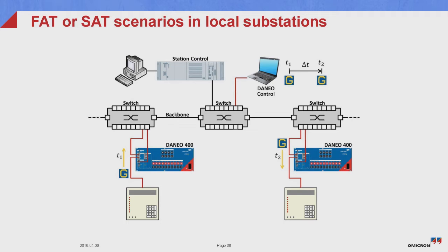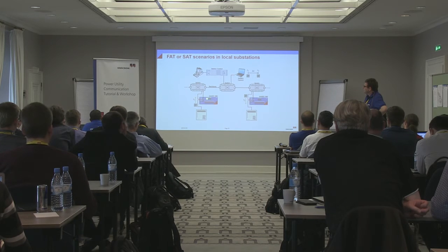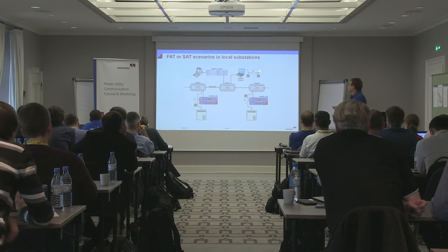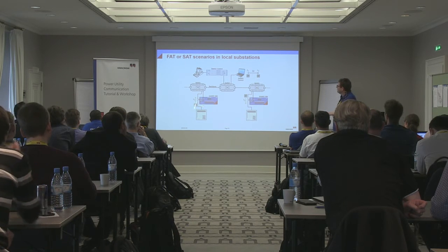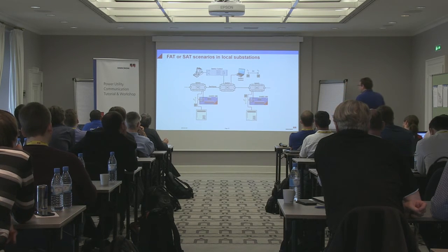This allows you, for instance, in such an infrastructure, that you really can do in your substation where the switches are working together. You can connect here, you can work with several devices, or if it's close together, then of course you have several ports, and you really can measure what is the propagation delay for that GOOSE issued here going to that point. There are several customers and more that really say, this is something I really want to know.